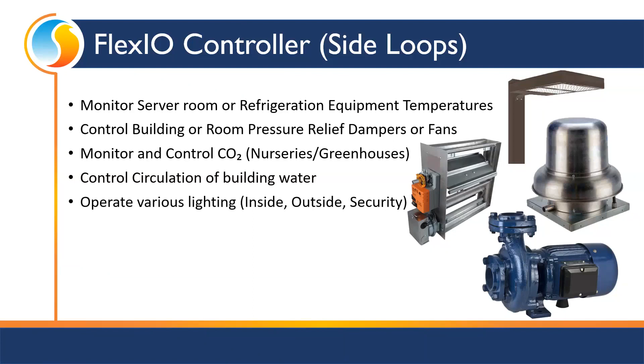We could use it as a lighting controller, operating various lighting, whether it's inside, outside, security. We can have it following a schedule. We can give an override button on the wall for someone to come in and push that button outside of the schedule. We've used the Flexio for parking garage ventilation control. All we need is sensors that can sense what we need to detect, whether it's carbon monoxide, whether it's explosive gases, that kind of stuff.